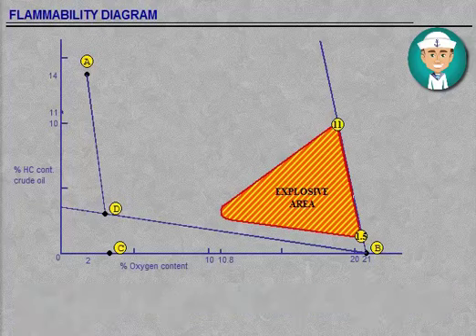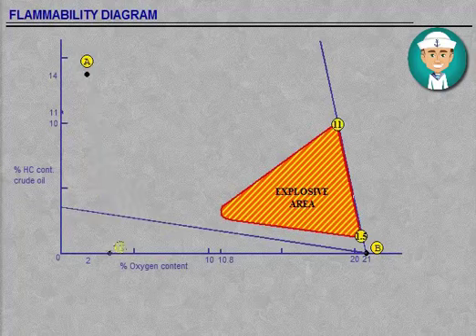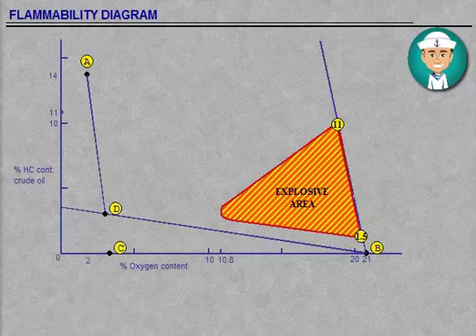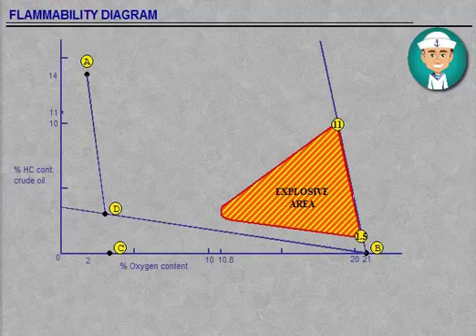Continue to measure the tank atmosphere. At point D, the inerting is to be stopped and the air venting starts. All measurements taken from now on will follow a straight line from point D to point B.